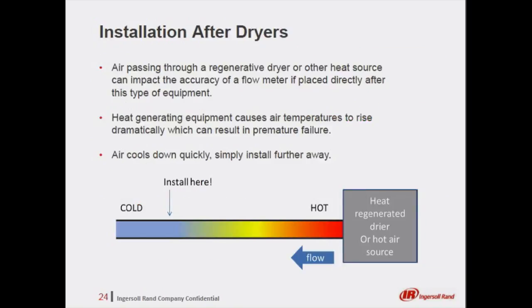Compressed air passing through a regenerative dryer or other heat source has a tendency to elevate the temperature, which can affect the accuracy of the flow meter. Installation of the flow meter further downstream from this type of equipment will assure that the air has cooled sufficiently for accurate measurement.